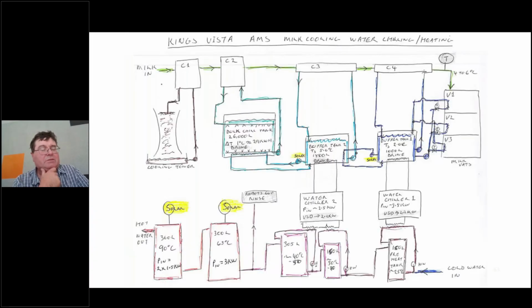Okay, as part of what was happening, we had strategic plans in place. We had been using solar for a little while and kept adding more and more to the system, but we had strategies in place to eventually go very close to off-grid and to update our refrigeration heating system. 2 government grants became available that enabled it to happen quicker, all within the space of 6 months. So this was the change to the cooling system. We ended up swapping everything around from being 2 large refrigeration units, about 13.5 horsepower in compressor power, down to 4 horsepower in compressor power.